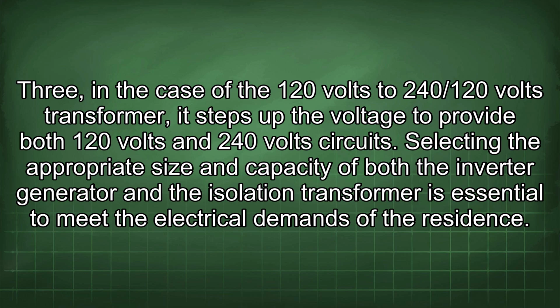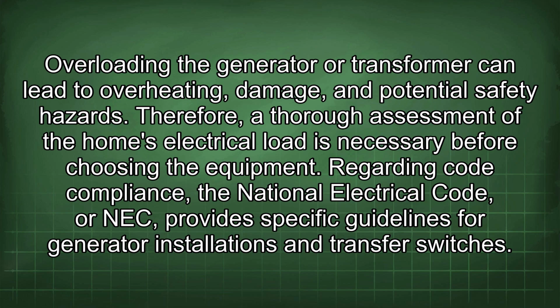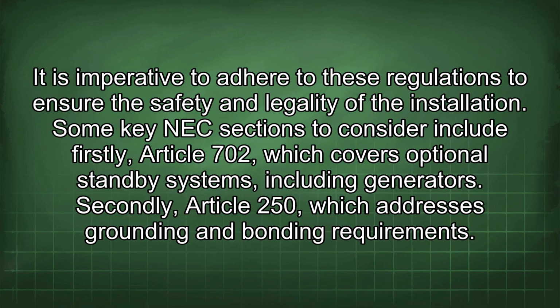Selecting the appropriate size and capacity of both the inverter generator and the isolation transformer is essential to meet the electrical demands of the residence. Overloading the generator or transformer can lead to overheating, damage, and potential safety hazards. Therefore, a thorough assessment of the home's electrical load is necessary before choosing the equipment. Regarding code compliance, the National Electrical Code, or NEC, provides specific guidelines for generator installations and transfer switches. It is imperative to adhere to these regulations to ensure the safety and legality of the installation.